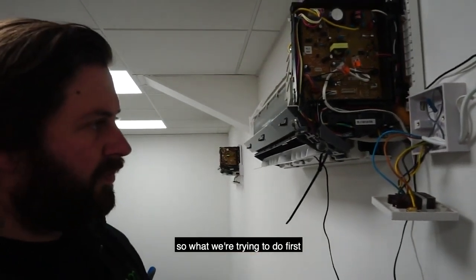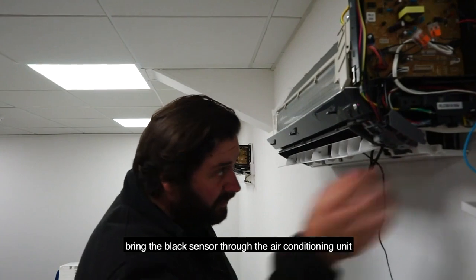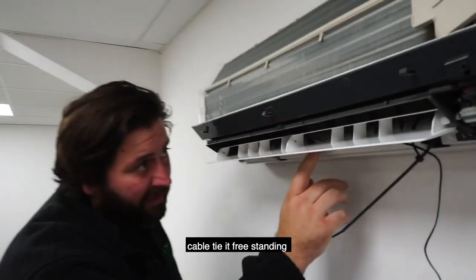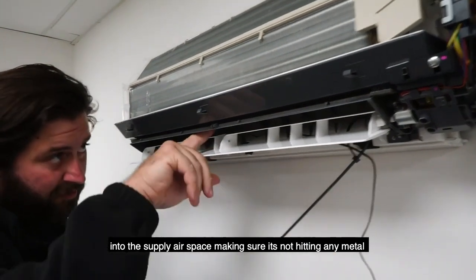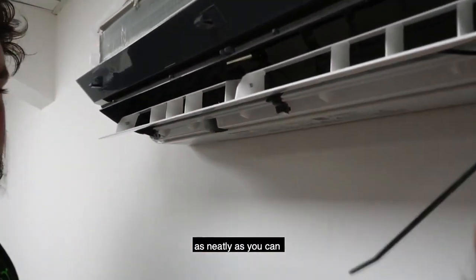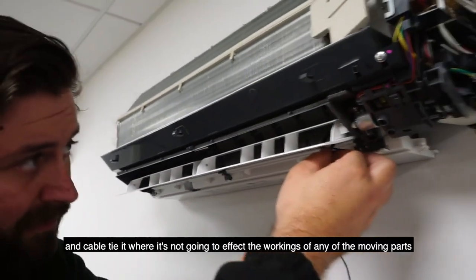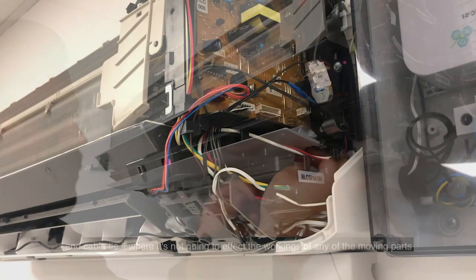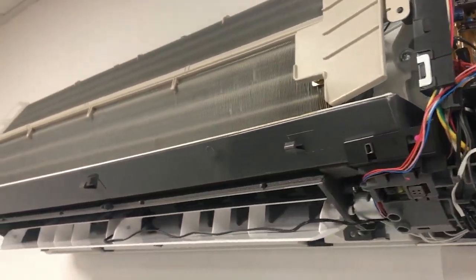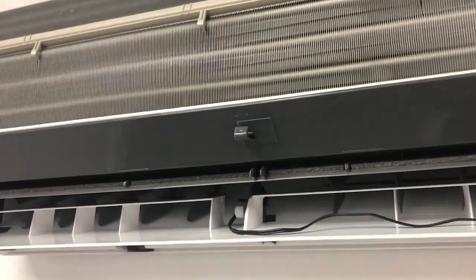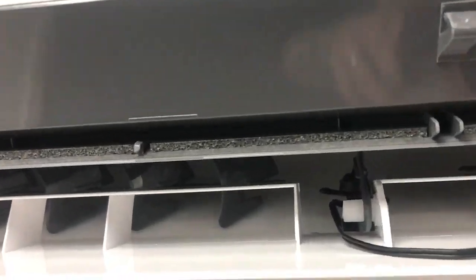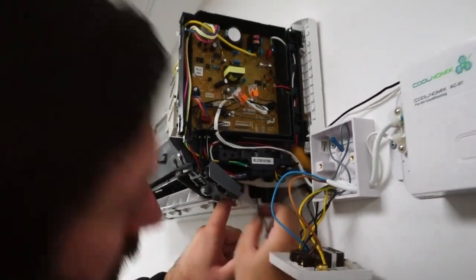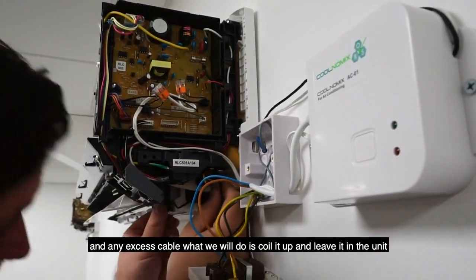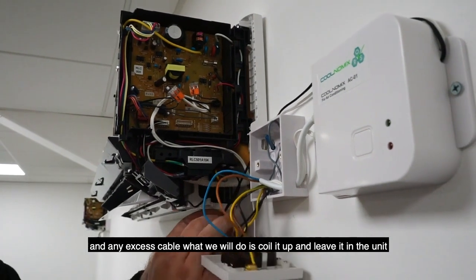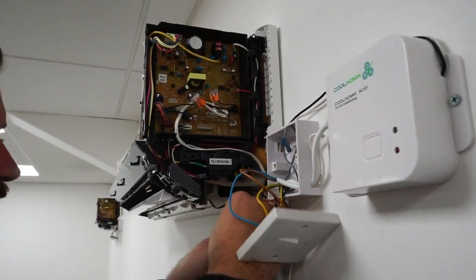So what we're trying to do first, bring the black sensor through the air conditioning unit, cable tie it in freestanding into the supply air space, make sure it's not hitting any metal, as neatly as you can, bring it back through the unit and cable tie it where it's not going to affect the workings of any of the moving parts. Finally, what we're trying to do is bring the supply air cable back through the unit, and any excess cable, what we'll do is coil it up and leave it in the unit.